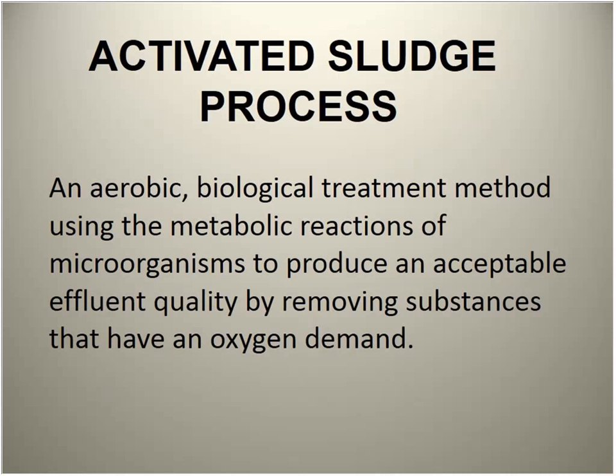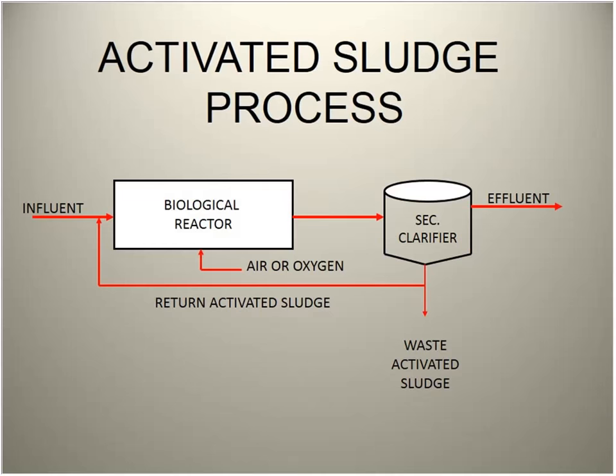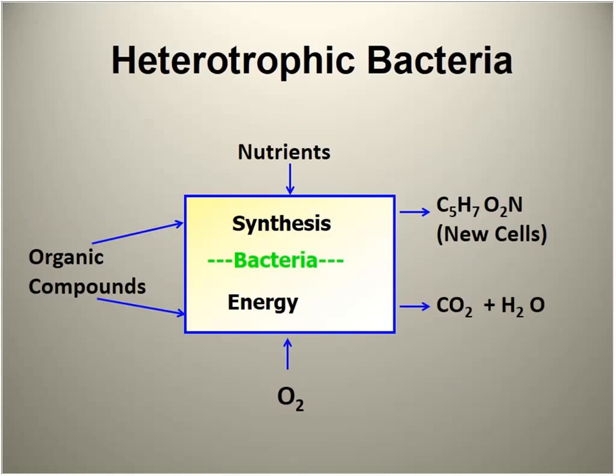When a plant has to upgrade for phosphorus removal, if it's a fixed film process they will add an activated sludge system because that's where we have ultimate control. We still have our biological reactor, we still have to provide air to these organisms, and we're going to have to provide more air. We're largely talking about two different types of bacteria: heterotrophic bacteria that go after carbonaceous BOD, and we need a certain amount of nutrient to keep the organisms in good shape.